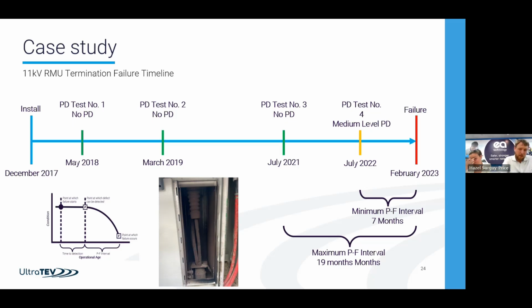So the full answer to how often comes down to risk. If this is your incoming board, sole supply to your factory, and it would cause a very bad day if it went offline, you might check every couple of months, even every month. If it's a completely redundant circuit, low risk, it might be every couple of years. That really depends on your criteria.